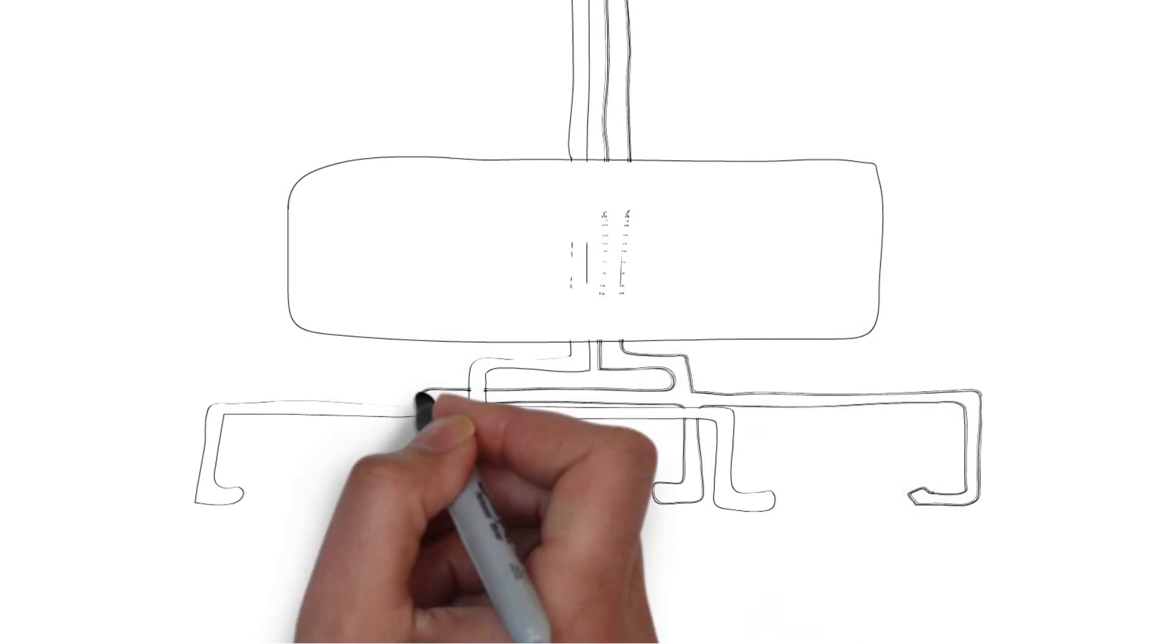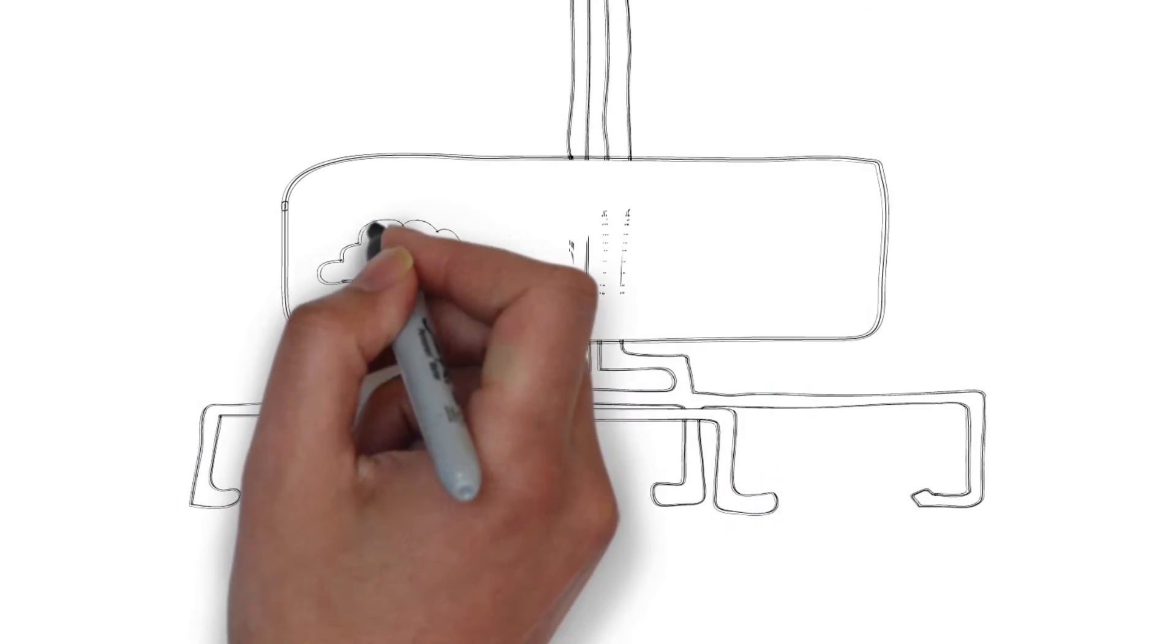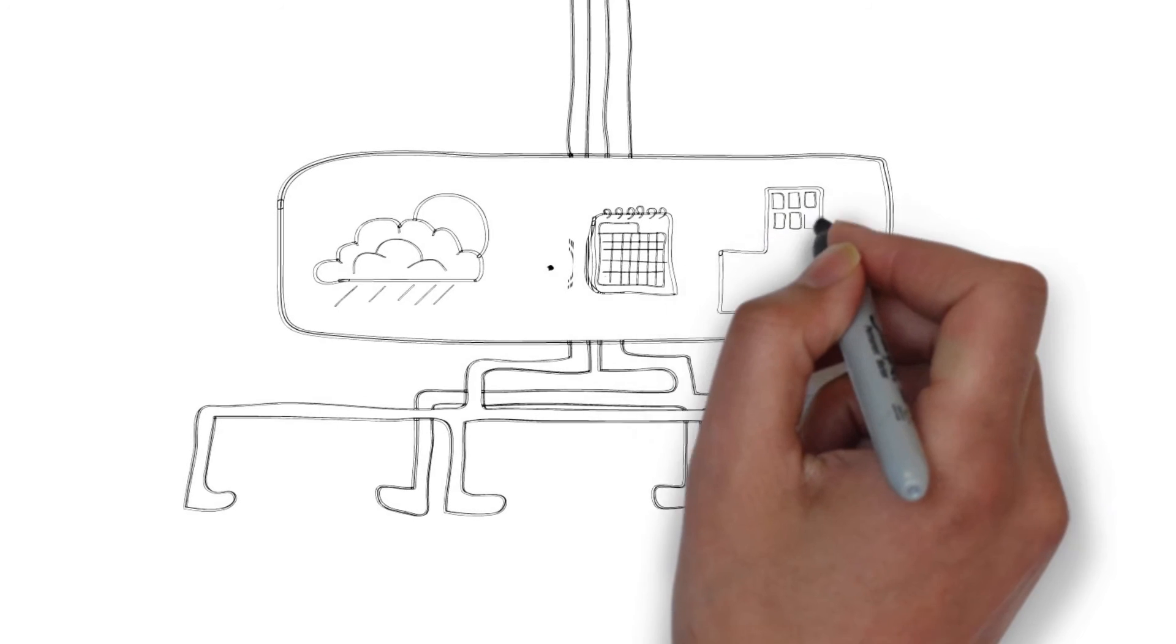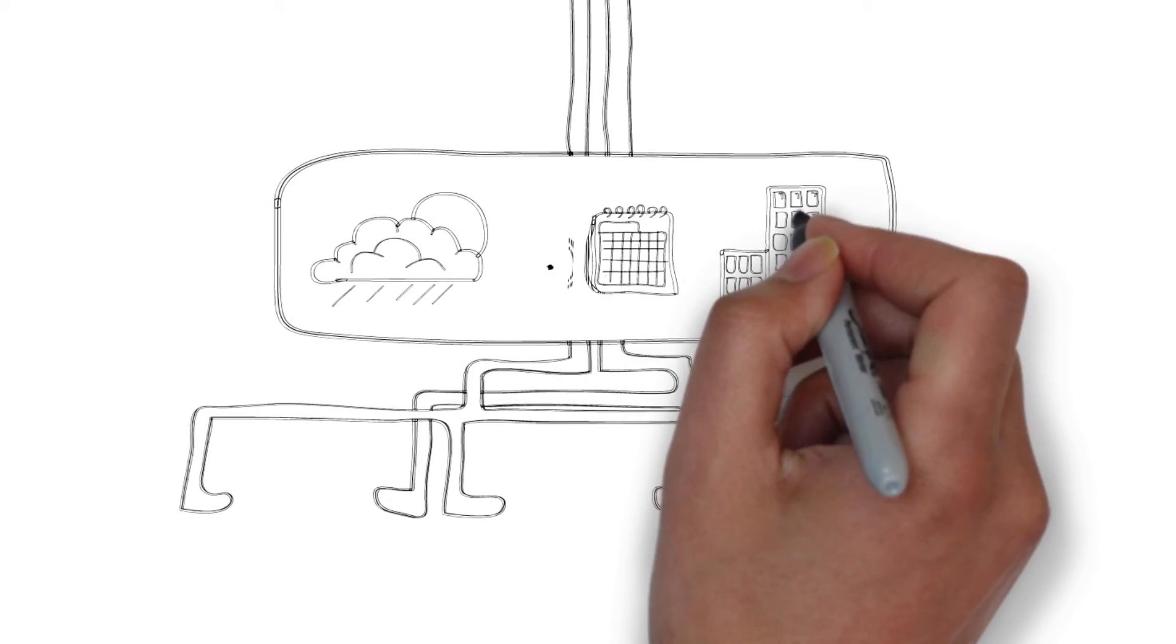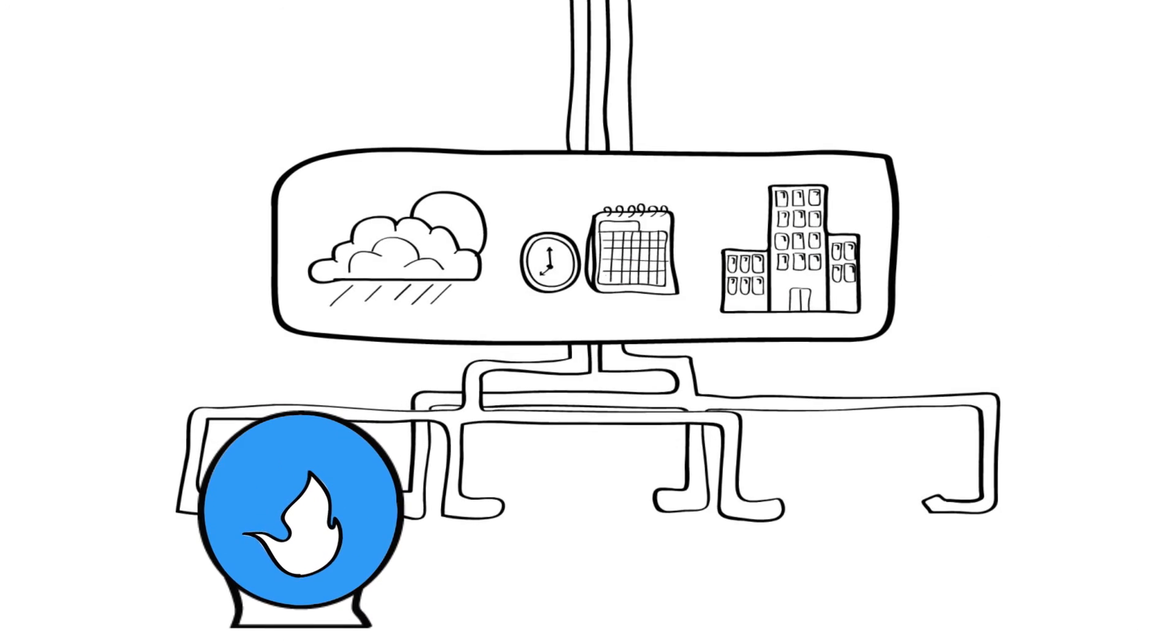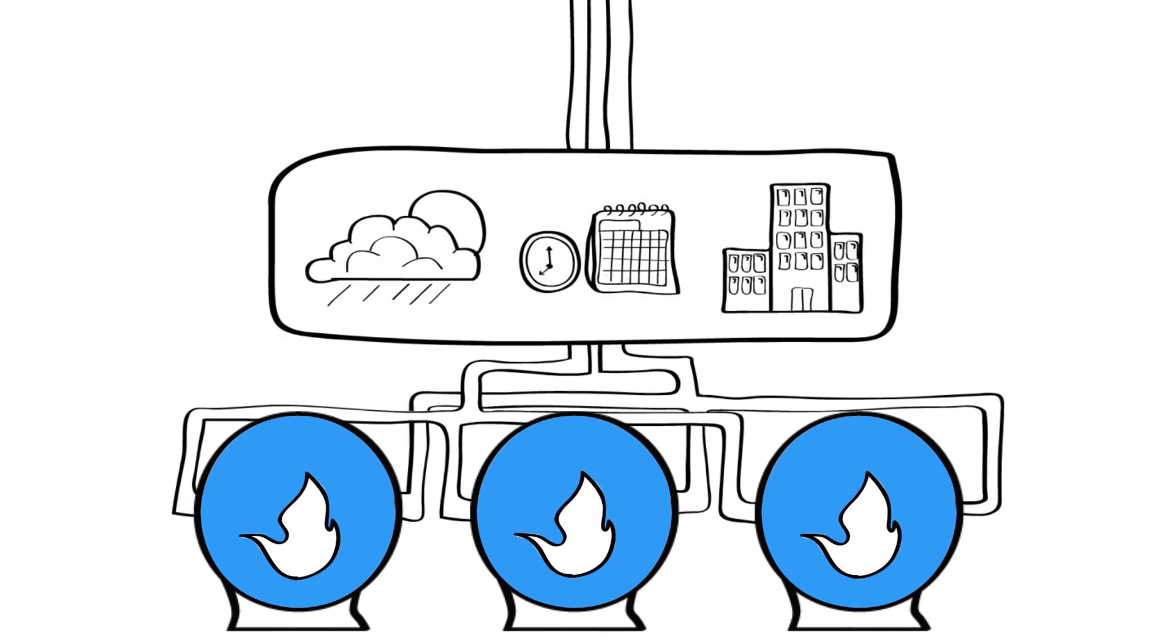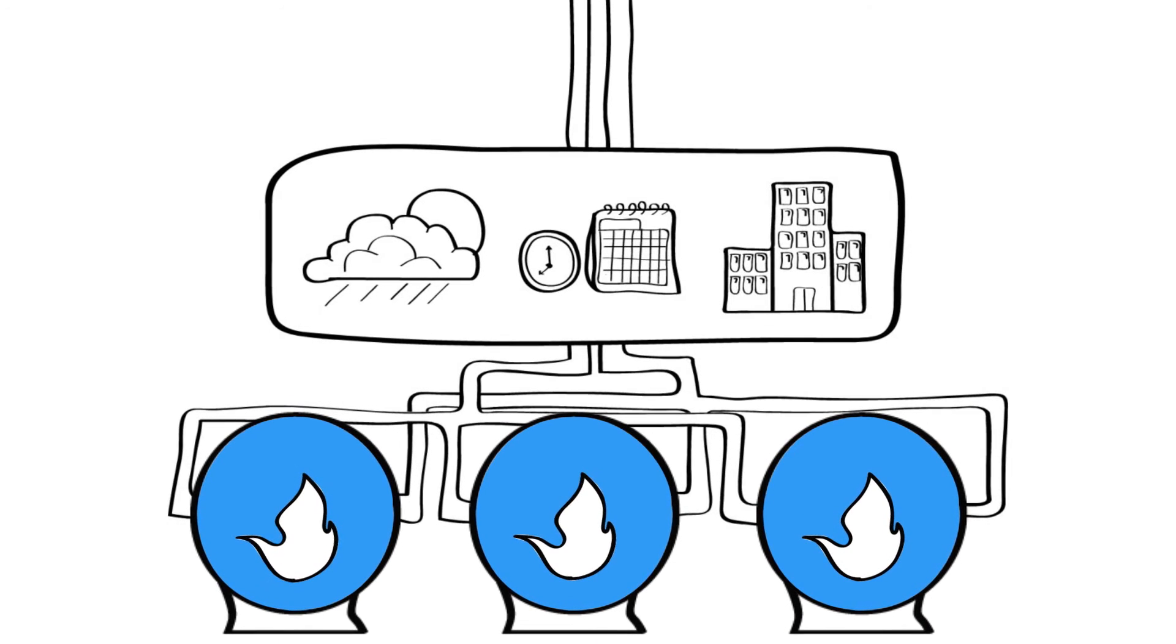Well, BMS systems, weather compensation systems and sequencing systems typically use control strategies which take measurements and control of all the boilers combined, but don't typically measure and control each individual boiler. Essentially, they macro manage the boilers.